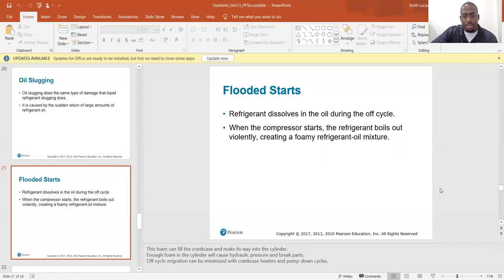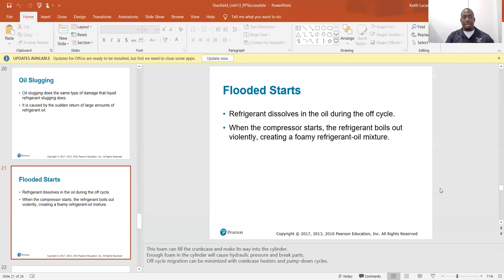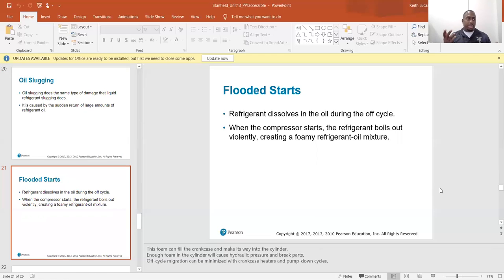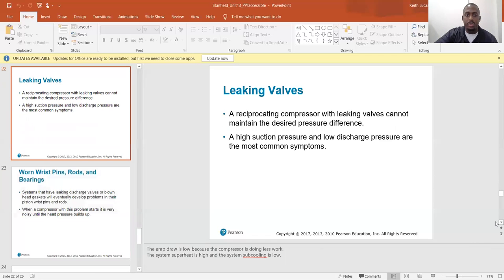Off-cycle migration can be minimized with crankcase heaters and pump-down cycles. The crankcase heater is a small electric heater around the crankcase where oil collects in the compressor. Its purpose is to keep refrigerant vapor from condensing into a liquid during the off cycle — because if liquid refrigerant is present when the compressor starts, it can damage internal parts. The crankcase heater boils off that refrigerant and prevents liquid from forming in the oil during the off cycle.